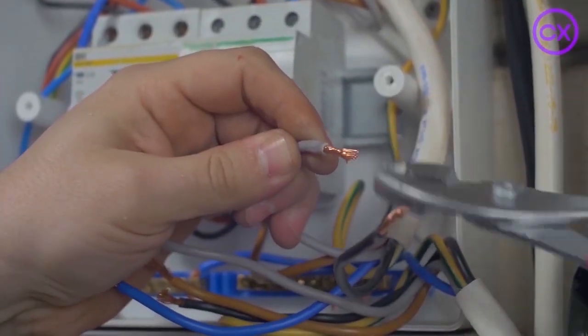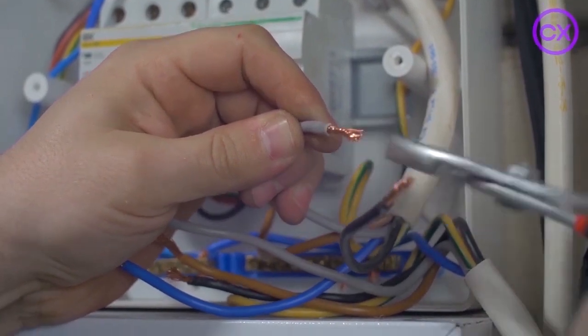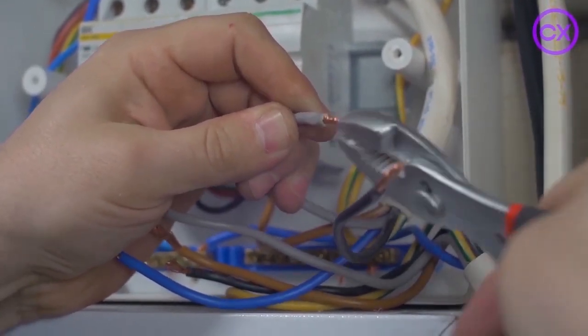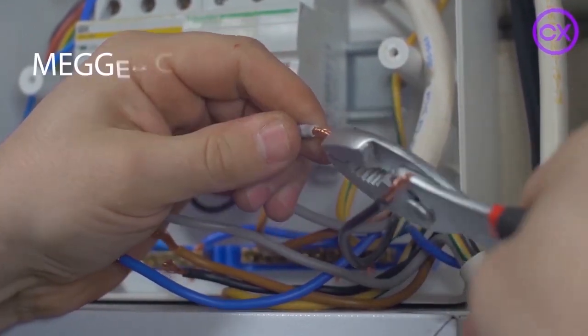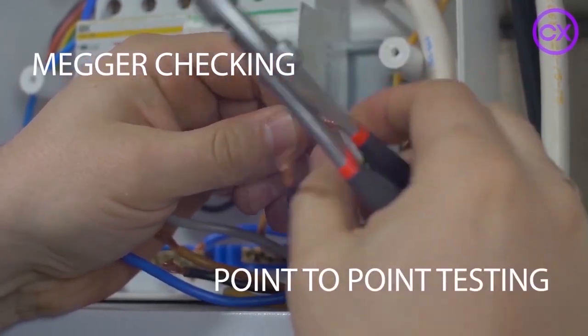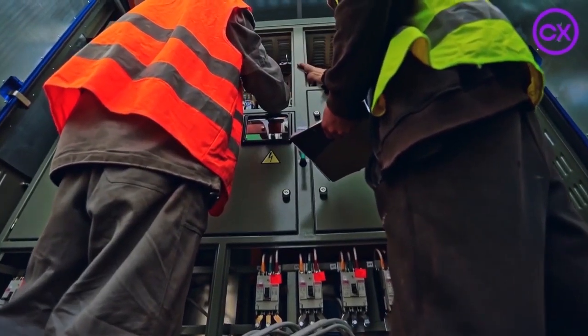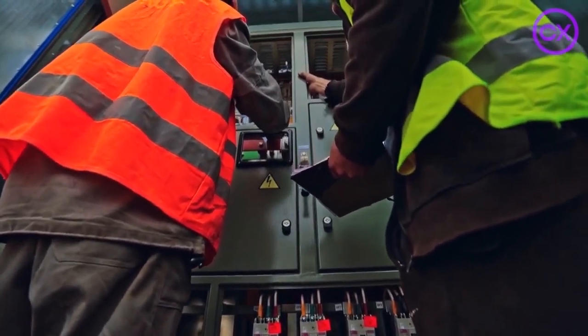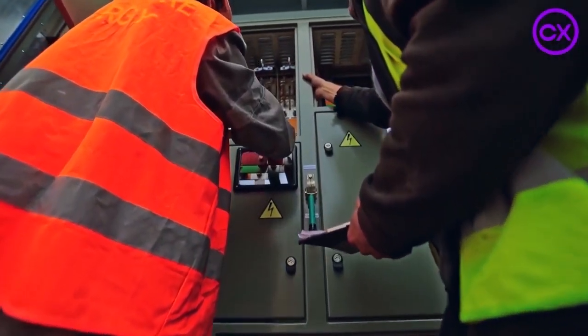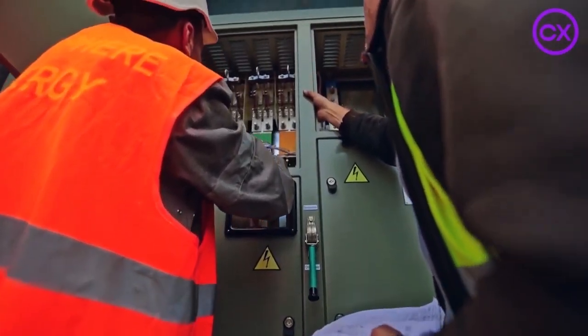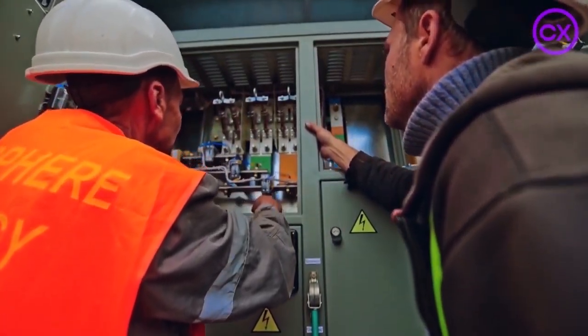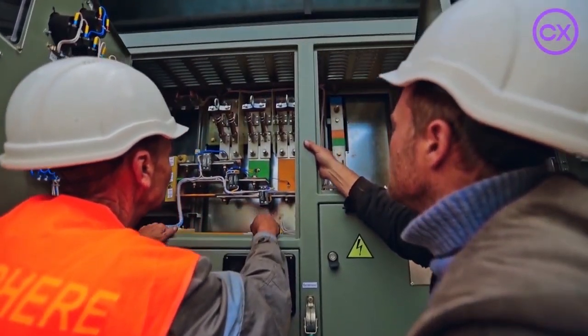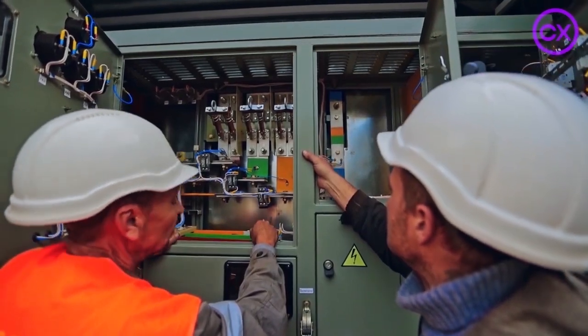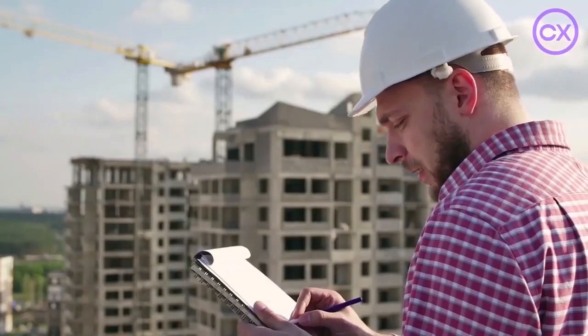An example of an electrical ITP is a checklist that lists all the checks to be done on cables after they've been pulled. So this includes Megger checking and point-to-point testing. Megger testing confirms that there is no damage of the cable and that its dielectric properties have remained intact after installation. And point-to-point testing verifies that the cable is terminated properly to the correct terminal blocks within the automation cubicle.